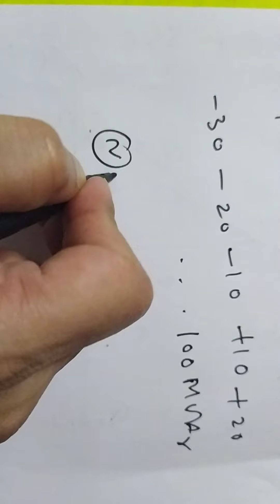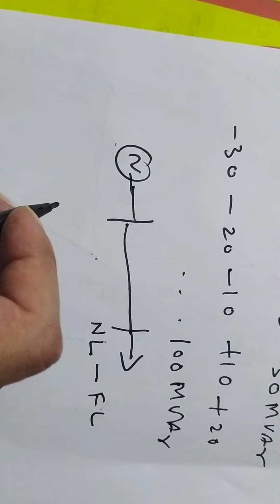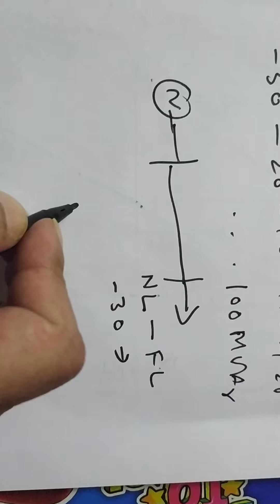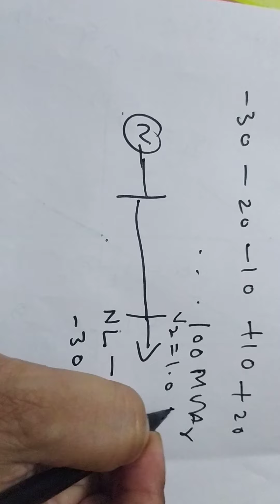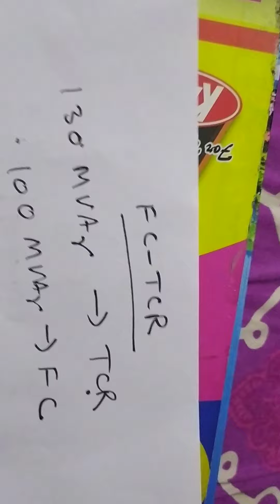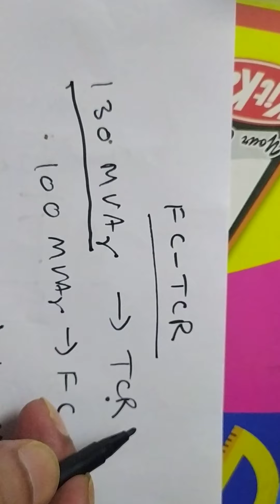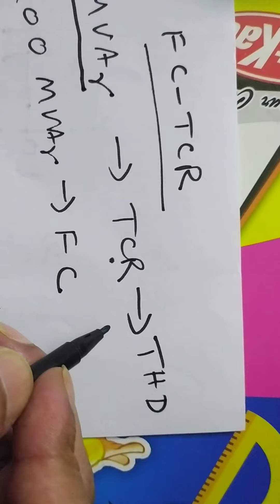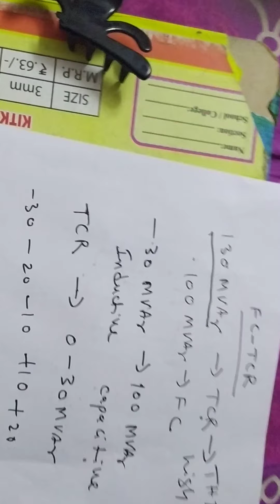Therefore, by providing the control for a long transmission line, from no load to full load it is operating. From no load also you can provide minus 30, and hence you can strictly maintain the bus voltage V2 equal to 1.0 pu all the time by using the FC-TCR type SVC. But of course here 130 MVAR is the capacity of the TCR, so the THD injection into the system is very high. This is the disadvantage of your FC-TCR type SVC.